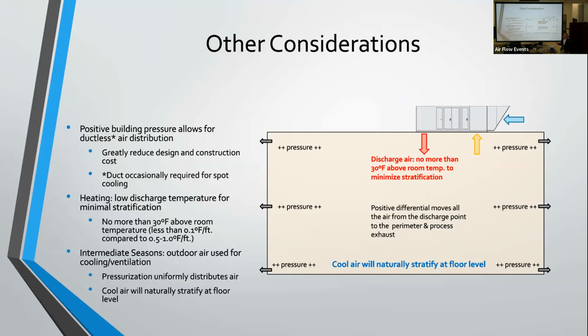Yeah, there are some other systems out there that try to heat spaces using 160-degree discharge temperatures, the max you can do, which can cause stratification issues. So aim for that 30-degree differential, and you'll see a lot less stratification in that space. One other thing: in your intermediate seasons, when you're using outdoor air to ventilate and cool the space, you're still pressurizing that space, but it's nice to know that your cool air is actually going to stratify naturally towards the floor level. So something to keep in mind.